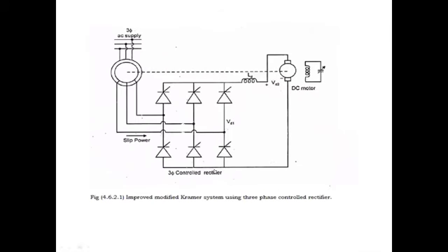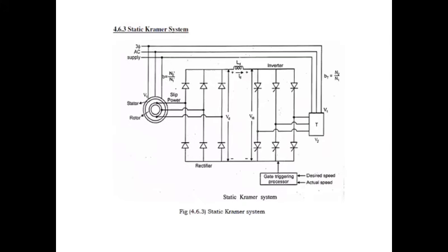At the lowest speed required from the drive, VD1 will have maximum value, which ensures inverter operation at the highest firing angle, giving the highest power factor and the lowest reactive power at the lowest speed. This improves the drive power factor and reduces reactive power at all speeds in the speed range of the drive. The drive has application in fan and pump drives, which require speed control in a narrow range.